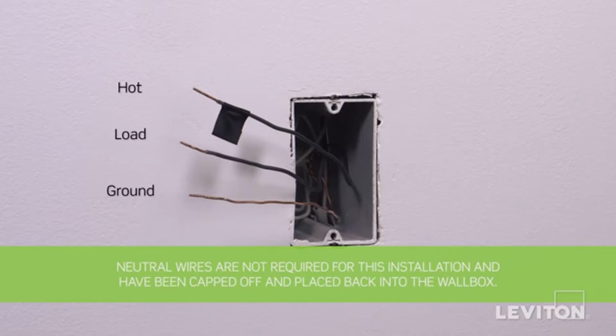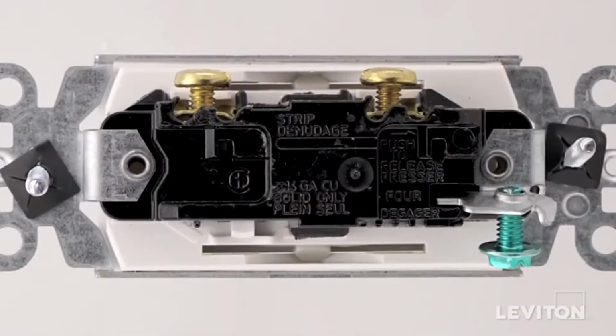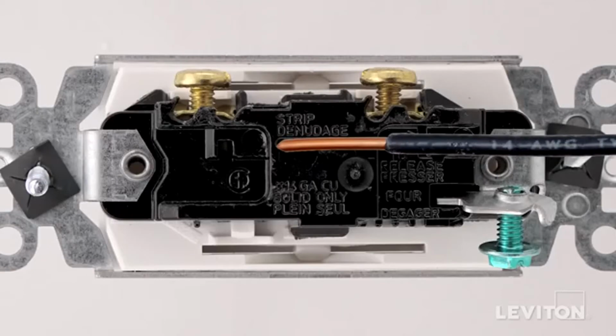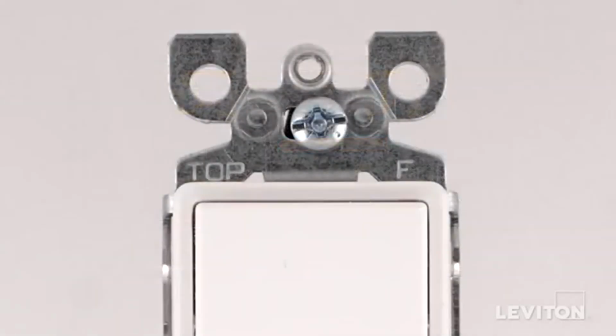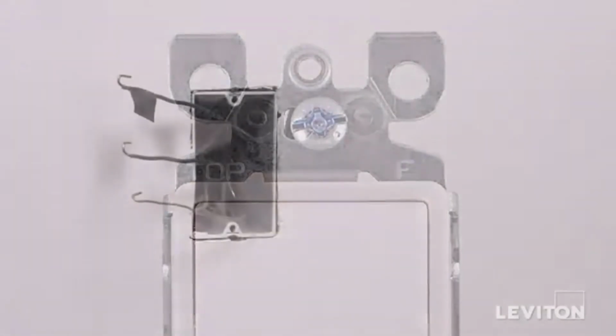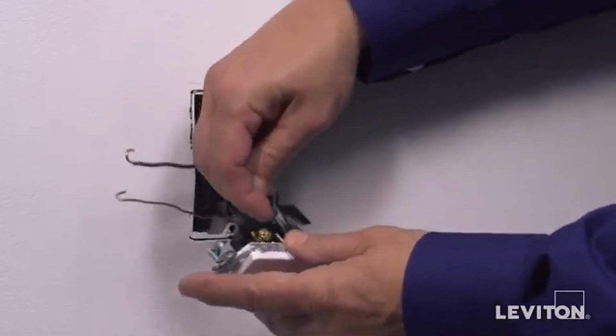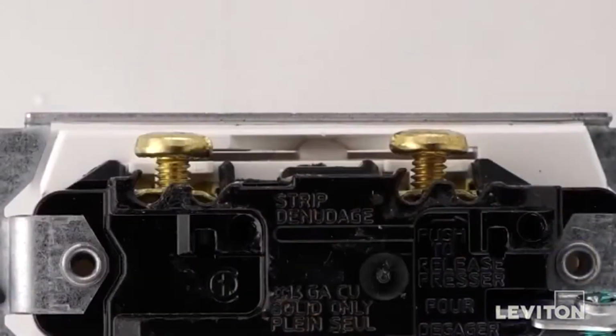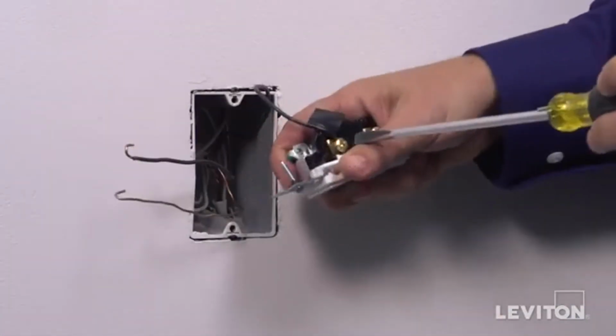Next, you need to be sure that the wires are prepared for installation. Start by making sure the wires are straight and stripped according to the strip gauge located on the back of the device. Before wiring, be sure the word top on the strap is facing up. To wire, first loop the hot wire clockwise 3/4 of a turn around either terminal screw. Tighten firmly.